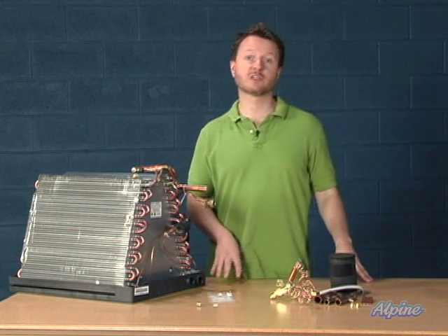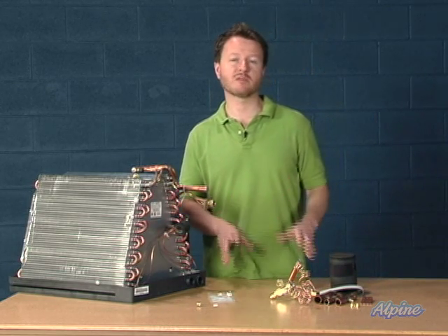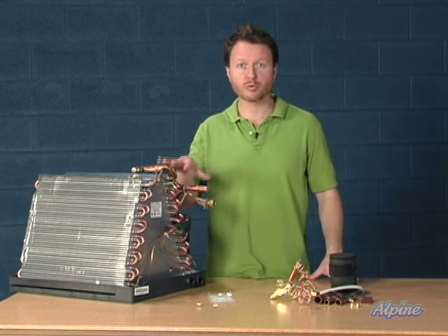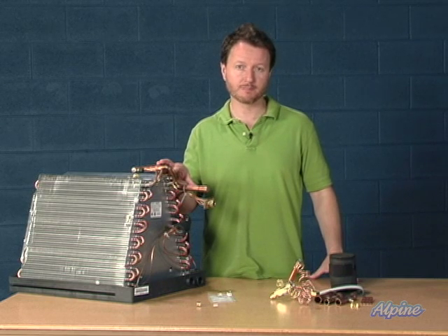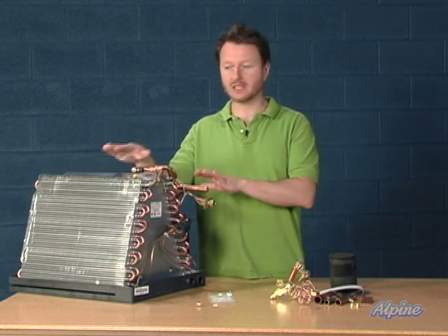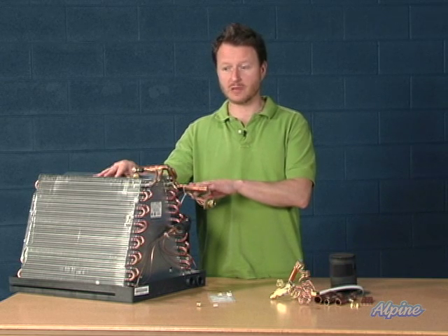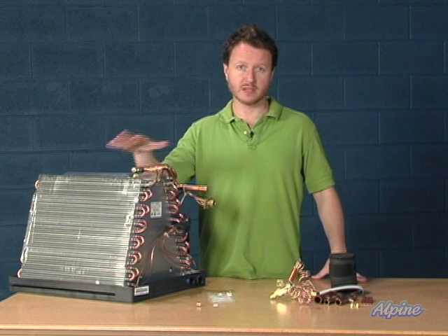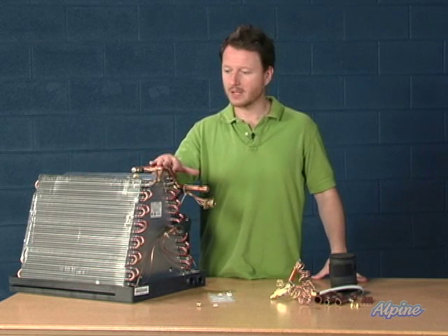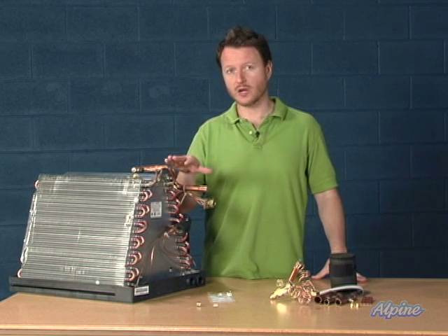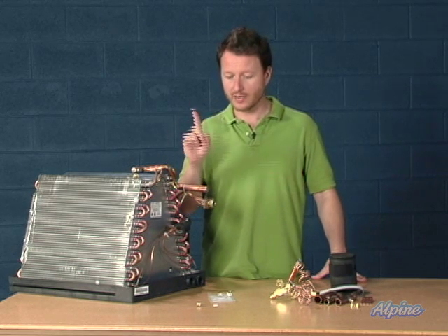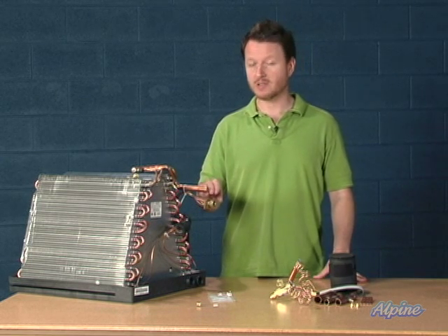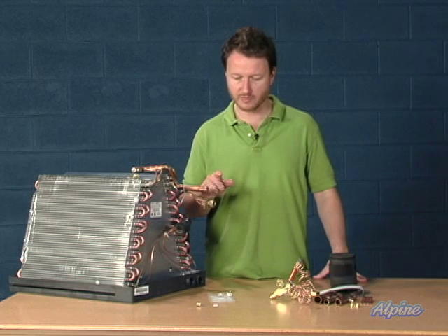Take a look at the manufacturer's installation instructions when you receive your equipment, or in advance of purchasing it, to figure out if you'll be using the orifice, which is already pre-installed in the evaporator coil, or if you'll have to change it. Typically, with higher efficiency systems especially, you'll have a larger tonnage indoor evaporator coil installed in the ductwork or in the air handler. If it's a larger tonnage compared to the unit outside, you're going to have to change the orifice that comes included in the system. Otherwise, you might just be using the one that's already in there. So take a look at that paperwork to figure out if you have to change or not.